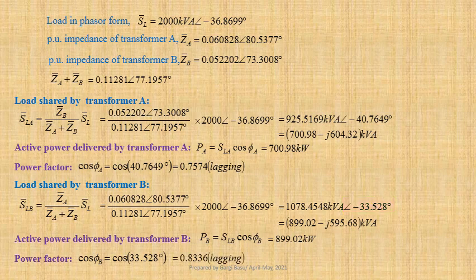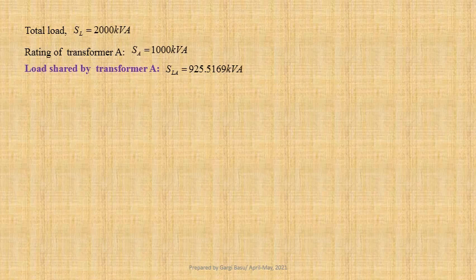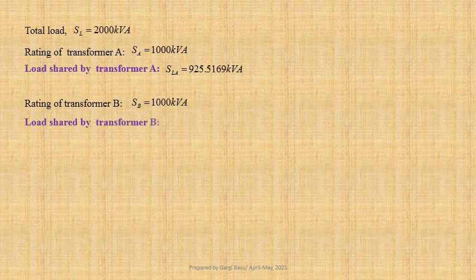Now let us note some interesting observations on the computed values. Given total load SL equals 2000 kilovolt ampere. Rating of transformer A, SA equals 1000 kilovolt ampere. Load shared by transformer A, SLA equals 925.5169 kilovolt ampere. Here we observe that transformer A is underloaded. Given rating of transformer B, SB equals 1000 kilovolt ampere. Load shared by transformer B, SLB equals 1078.4548 kilovolt ampere. Here we observe that transformer B is slightly overloaded.